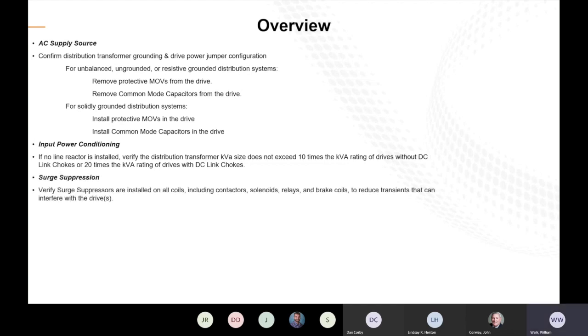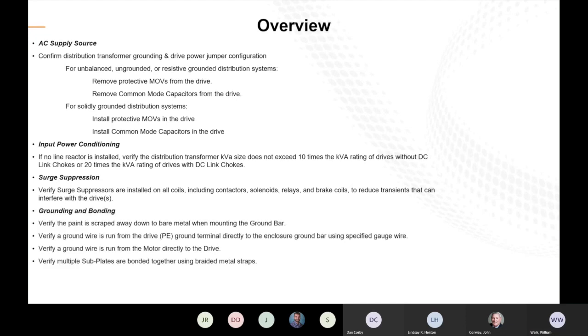Surge suppression: make sure you have proper surge protection installed on your VFD, and on all your coils, contactors, solenoids, relays, etc., so it doesn't interfere with your drive. Grounding and bonding: whenever you are grounding your VFD, ensure that some of the paint that your grounding cable is attached to has been scraped away so that we're solidly grounded to the system. Verify your ground wires run from your motor directly to the drive. Like I stated before, you have that ground on the right side of the VFD that should be used for that.